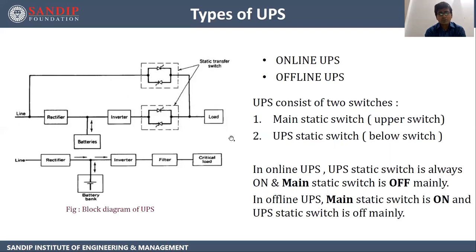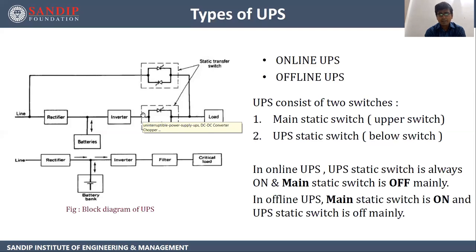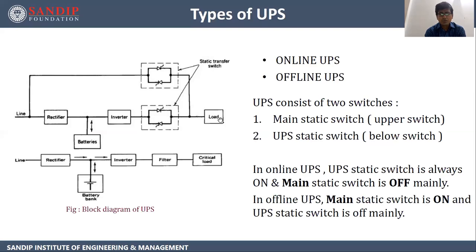Based on that, there are two types of UPS: Online UPS and Offline UPS. In online UPS, the lower switch — that is the UPS static switch — is mainly on, and the main static switch is mainly off. So the AC supply is fed to the rectifier, which converts it into DC. This DC is stored in the battery as well as passed through the inverter, so the DC gets converted into AC and fed to the load.